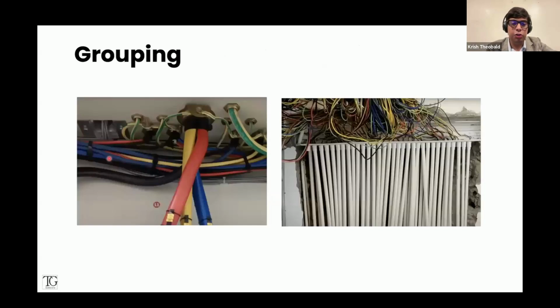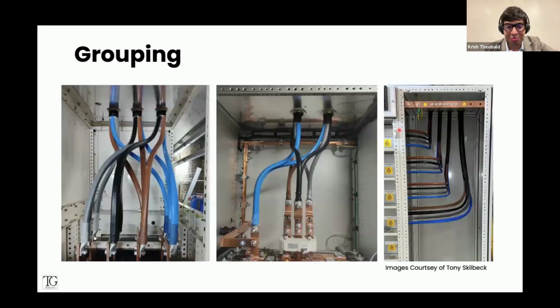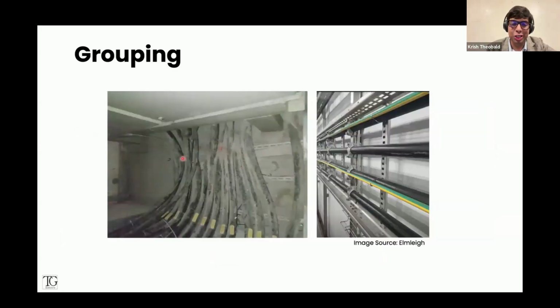So grouping. Well, we often see installations like this where the cables are very neatly tied up inside, but unfortunately very seldom are the actual grouping factors taken into account. And when you do this, you're essentially impeding the cable's ability to dissipate heat and maintain that maximum operating temperature, usually 70 degrees. On the other hand, you have this cluster where you've got so many conduits and so many cables. Same story here. This is an image from a friend of mine in the UK, Tony Skilbeck. So, if you want to mitigate grouping, in most cases you can do this by maintaining 2 times cable diameter spacing between cables. So if you have a 10 millimeter cable, just maintain 20 millimeters between. Then, in most cases, you don't need to take a grouping factor into account. We look at our cable shafts. Unfortunately, this is what we see. Simply maintaining a 2 times cable diameter spacing in most cases mitigates the need for grouping factors.